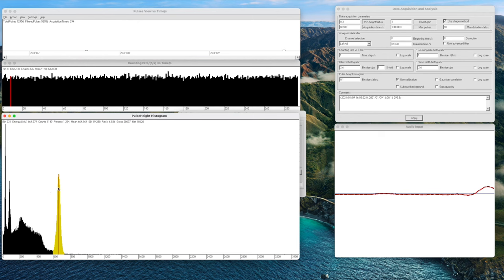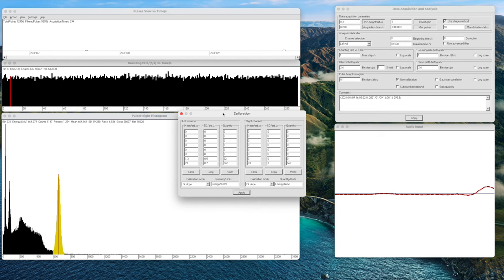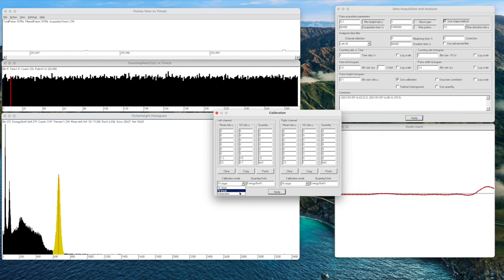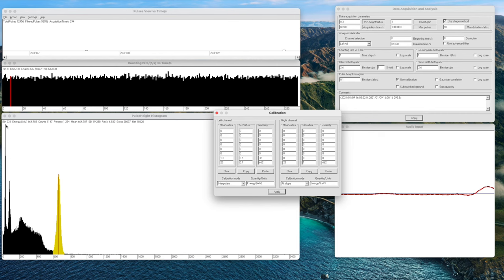We can use multi-point calibration and there is one thing to keep in mind here is that with multiple calibration points you will get a better result with the interpolate option rather than the linear option. That basically will give you, if you have let's say five known peaks, it will make it linear between the five peaks. So it'll be linear from this peak to this peak and from this peak to the next peak and so on.